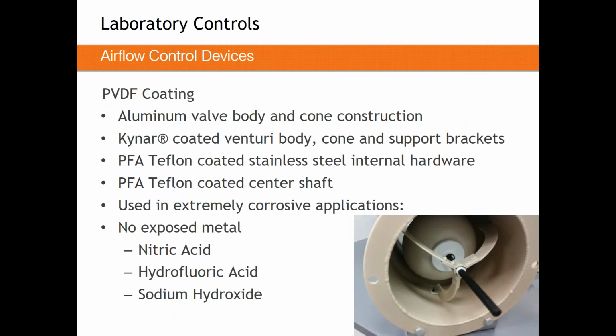Some systems, however, will need the highest level of corrosion or chemical resistance. We call that Kynar coating, or PVDF. In this device, all metallic parts are coated in either PFA Teflon or Kynar. This coating is monstrously expensive. On an 8-inch valve, the coating will cost more than the valve and controller combined. But what you're going to get is extremely broad spectrum, high level chemical resistance. So there are certain things where your only option is a Kynar coating.